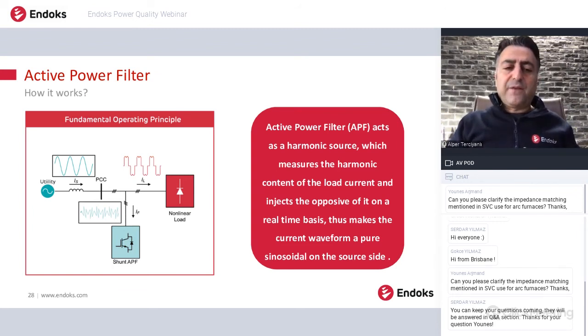So mostly the active power filters are low voltage devices, because since we are generating harmonics, the switching frequency of the devices is very high. For this reason, the active filters are mostly low voltage devices, and they are connected to medium voltage mostly with coupling or step-up transformers. Where we are using active power filters: mostly in IT industry, in hospitals, in data centers, because these harmonics, especially the higher order harmonics, can create problems on the telecommunication devices or the monitoring devices. So we are using active power filters.